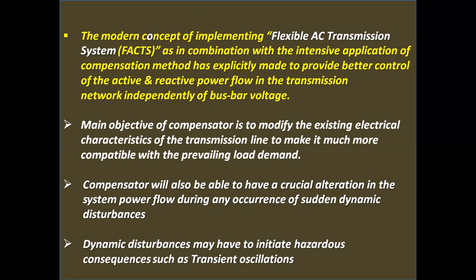independently of busbar voltage. The main objective of a compensator is to modify the existing electrical characteristics of the transmission line to make it much more compatible with the prevailing load demand. A compensator will also be able to make a crucial alteration in the system power flow during any occurrence of sudden dynamic disturbances. Dynamic disturbances may initiate hazardous consequences such as transient oscillations.